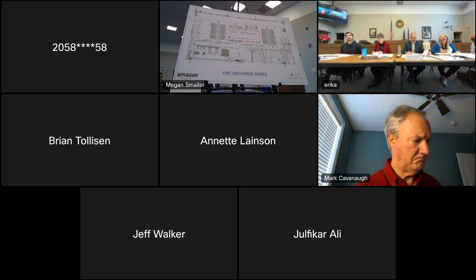I'll draw your attention to alternative number 3 on sheet 5. You'll see the allowable travel distance for this kind of facility, one story in height, is 400 feet. The actual largest travel distance from the most remote area on the floor is 254 feet.